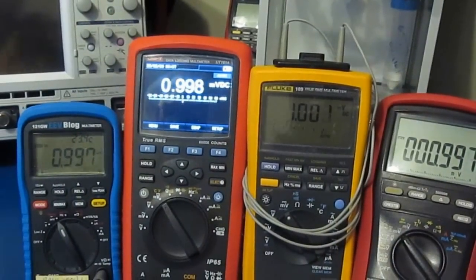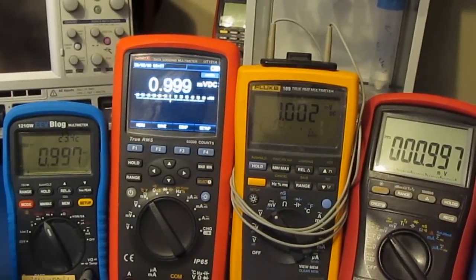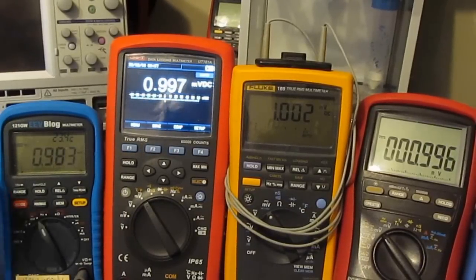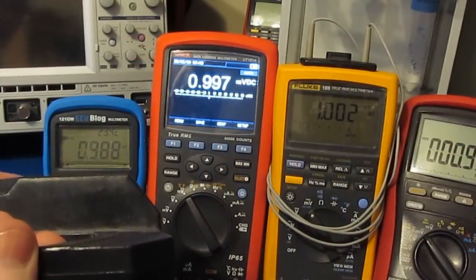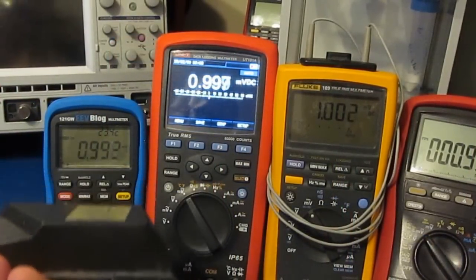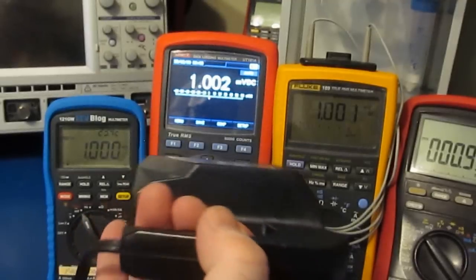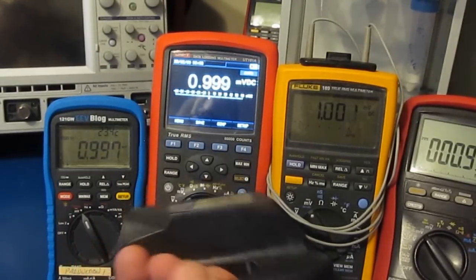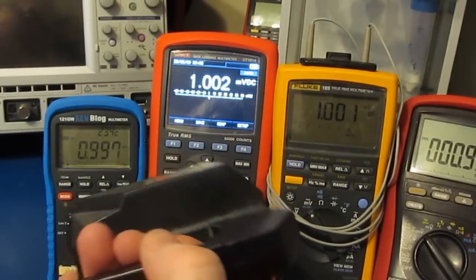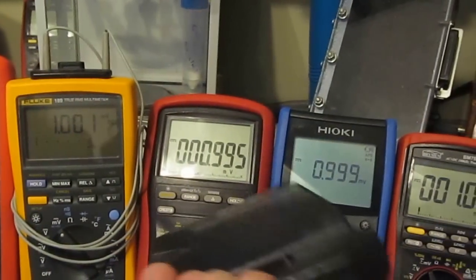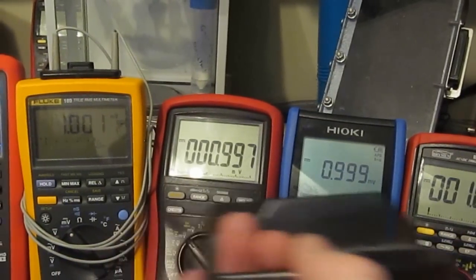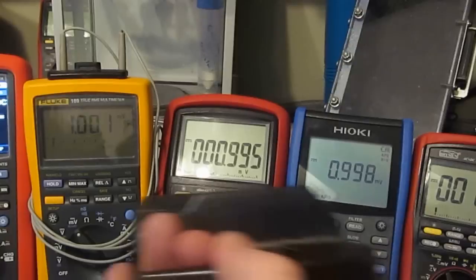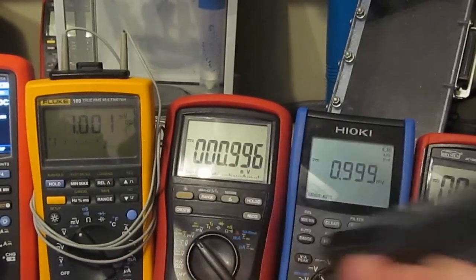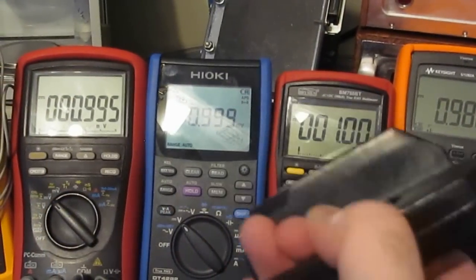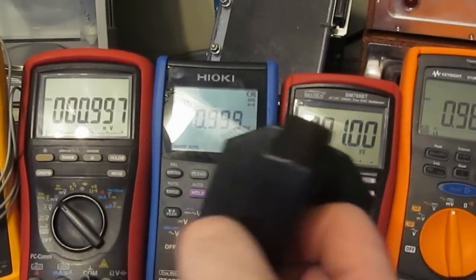The two worst, it looks like, are this UNI-T UT181A and this 121GW. Right there, I'm probably 4 or 5 inches away from the meter, same thing with the 181 - you can see it's got a pretty big effect on both of these meters. But our Brymen BM869s, as well as the new Hioki, are basically immune to this. Same thing with our brand new Brymen BM788 BT. So it looks good.